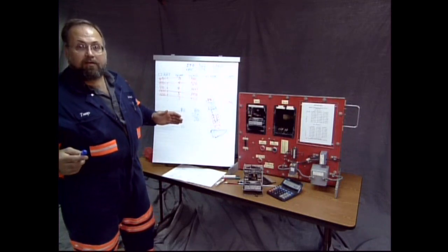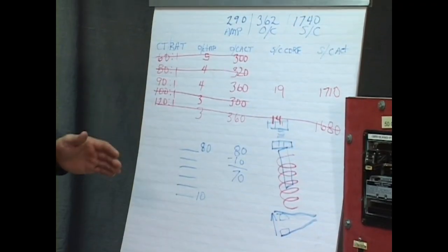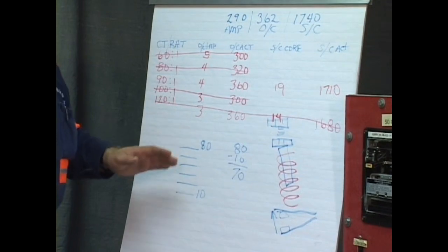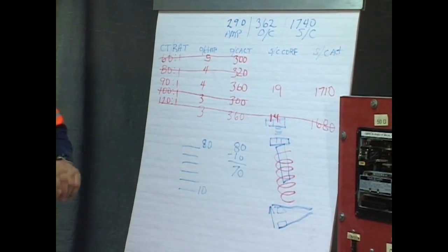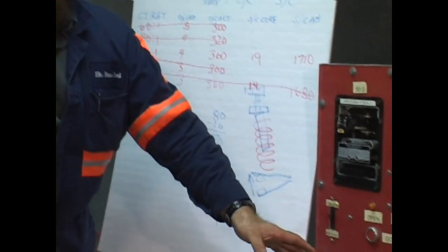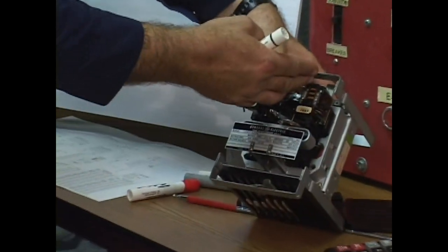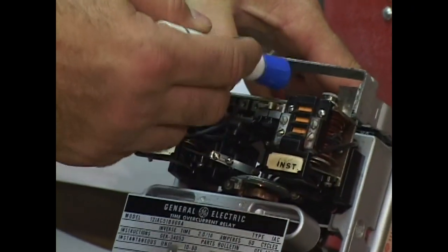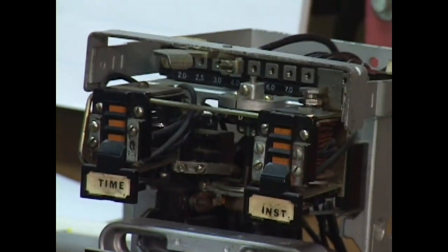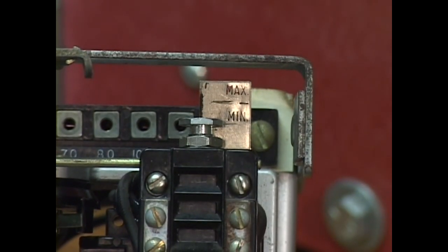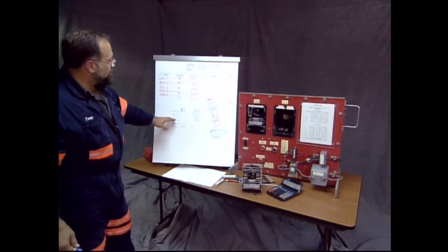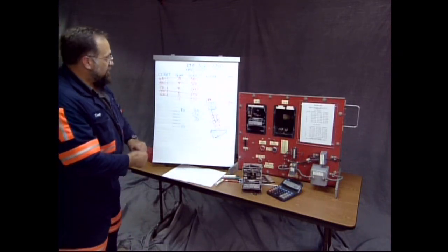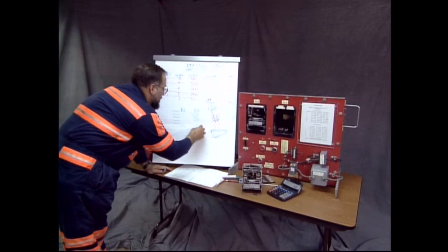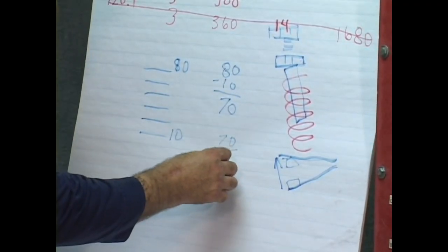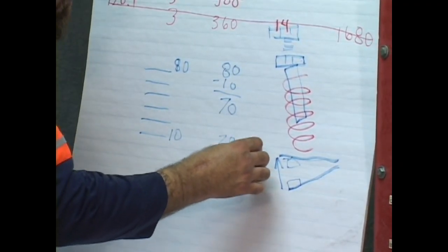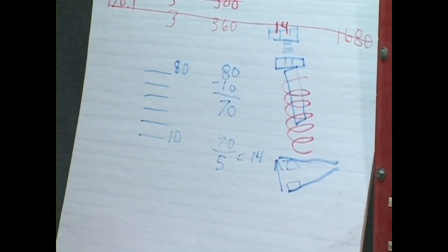You don't have a house fire every day. This is not going to be tripping every little bit. So err on the light side. There are basically 5 increments of measure, and I use the thickness of the adjustment bolt head as one increment. There are basically 5 of those between minimum and maximum. So let's divide our span by 5. And that gives you an increment is worth 14 amps.